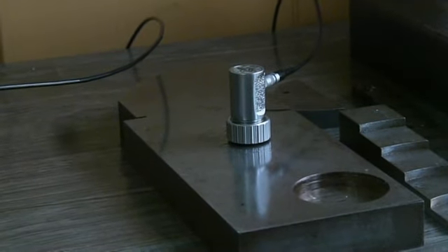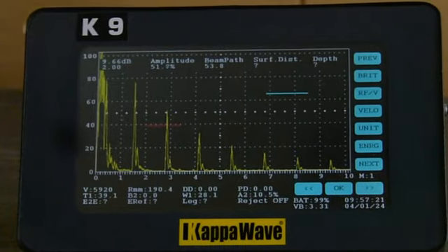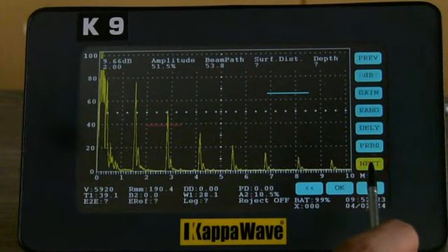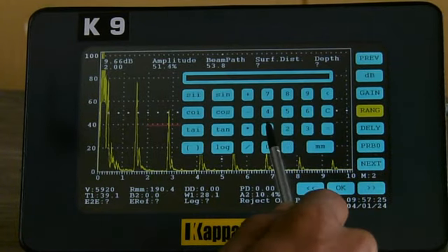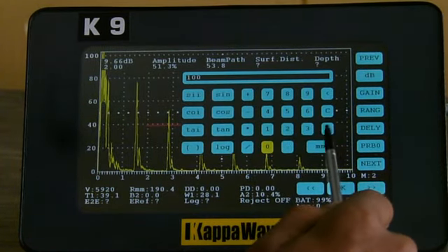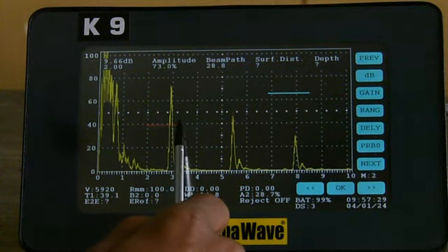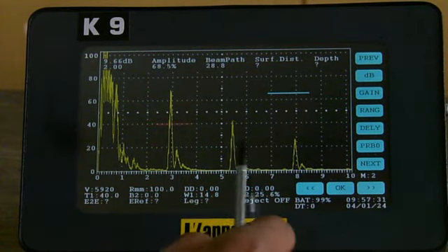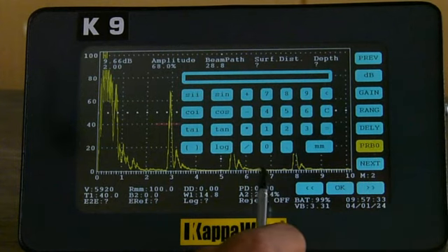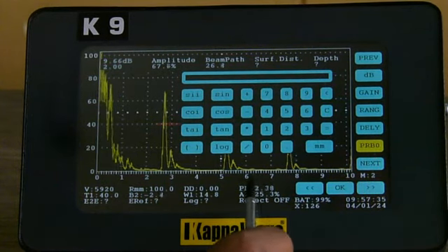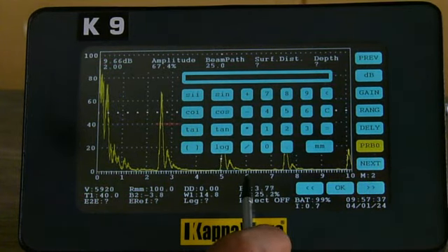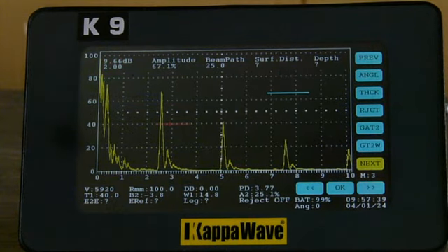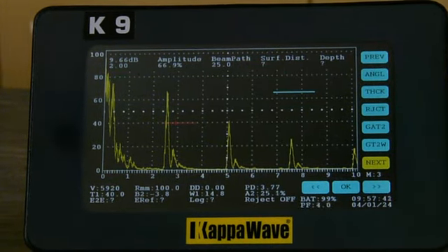Okay, now I'm using a 4 megahertz normal beam probe on the V1 block, and we will now calibrate the range to about 100 millimeter. So click and enter 100 millimeter range. Place the gate on the first echo and try to read the beam path above. It is not exactly 25, so we will use the probe zero control. Slowly drag and bring it to read 25 millimeter.